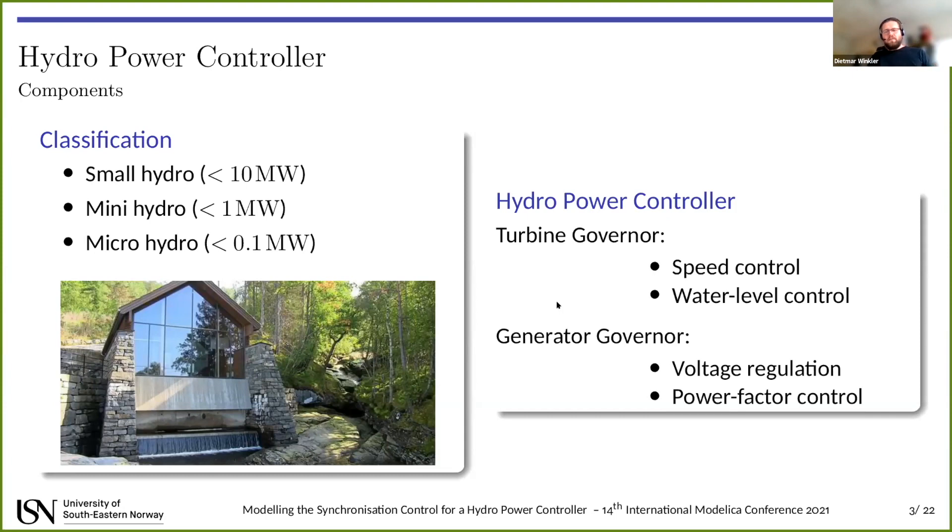The hydropower controller typically consists of two parts. You have a turbine governor and a generator governor. The turbine governor takes care of regulating or controlling the turbine, whilst the generator governor is for the generator part. The turbine governor can have different functions included. In this case, we're talking about the speed control and the water level control, but there are also other functions available in typical hydropower controllers. The same for the generator governor. Here I'm going to talk about voltage regulation and the so-called power factor control, which you can also think of as part of the voltage regulation.